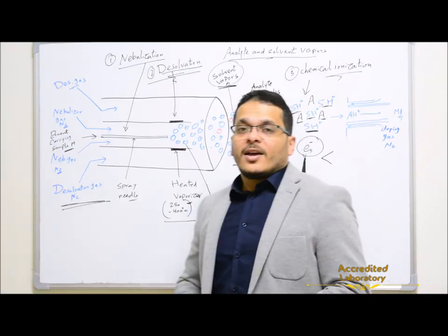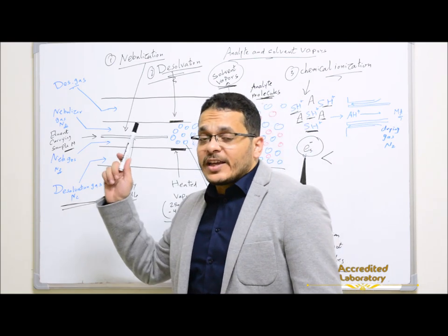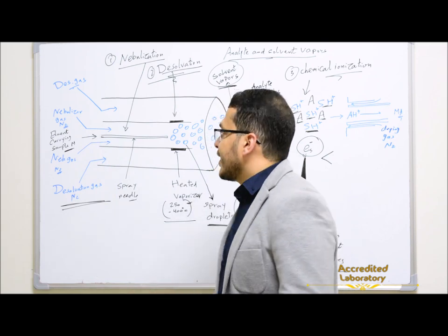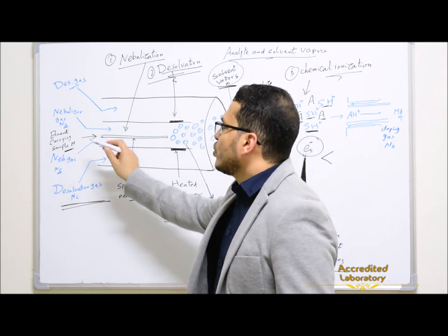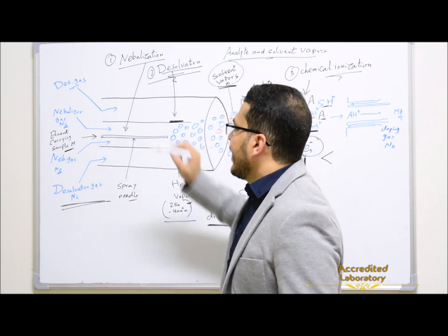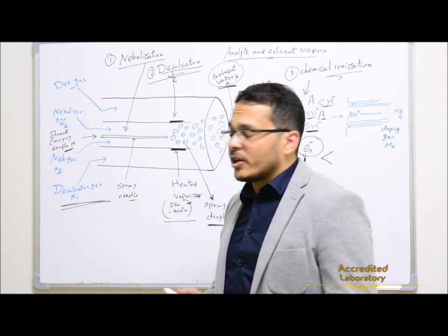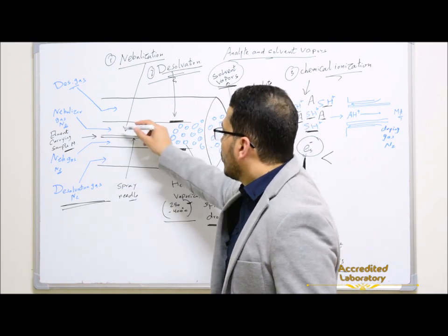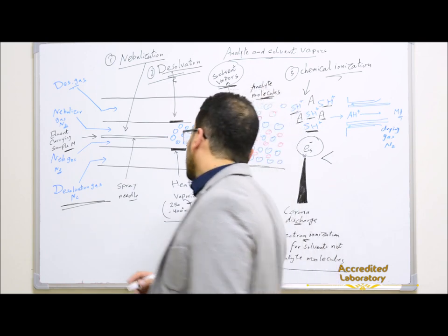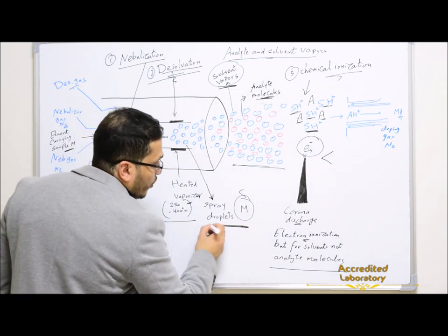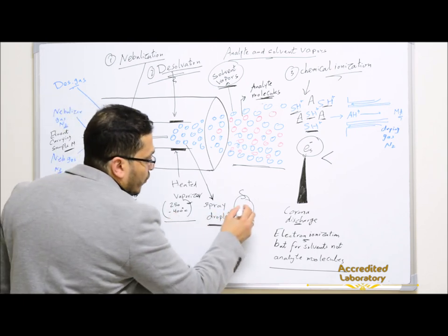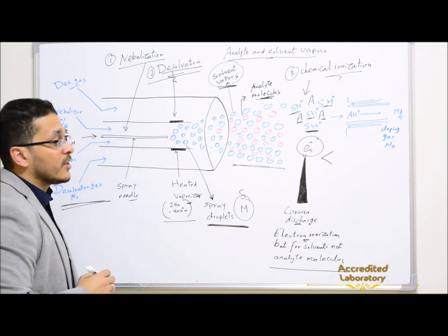Today's lecture will be about atmospheric pressure chemical ionization. As we see in this graph, mobile phase from HPLC carries the sample molecules, and the eluent carrying sample molecules will pass through the spray needle. By the effect of nebulizer gas, or sheath gas, or nitrogen gas, that shears around the eluent carrying sample molecules, converting them to spray droplets that consist of sample molecules surrounded by solvent molecules.